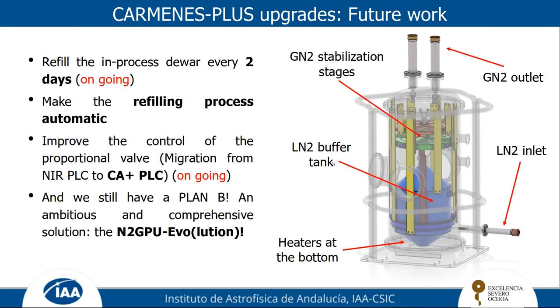We also want to have liquid inside the preparation unit before it goes inside and evaporates immediately, let's say. Now we want this first stage, shown in blue, to have an amount of liquid nitrogen, so we always have liquid nitrogen inside the system, and the refill happens inside the system and not outside. So it's important to always have liquid here and evaporate from the surface.